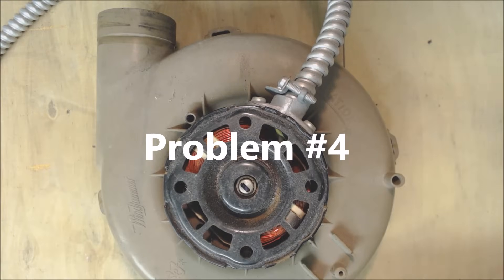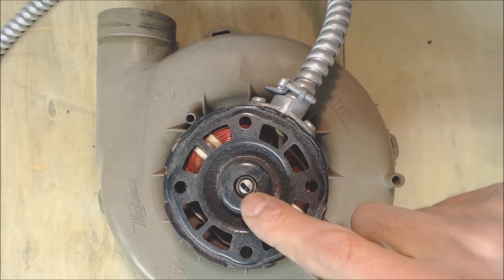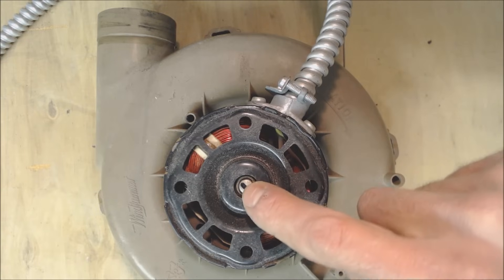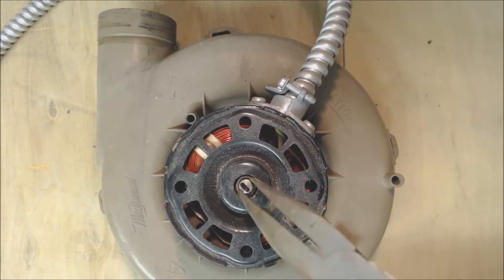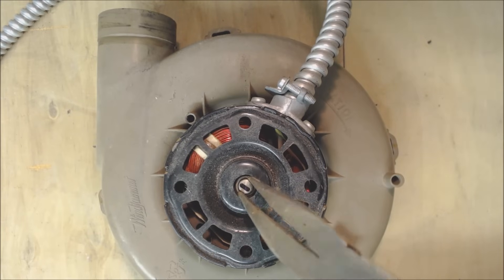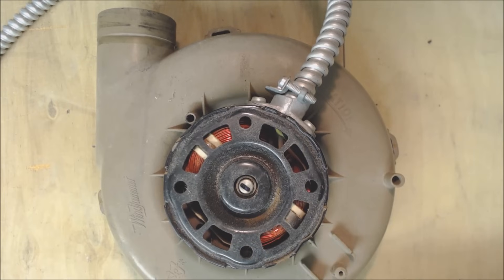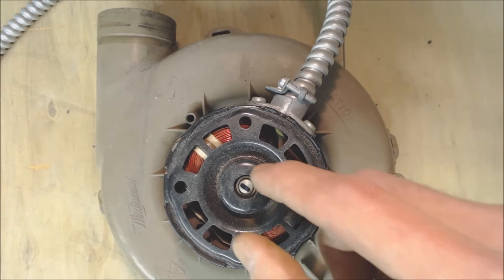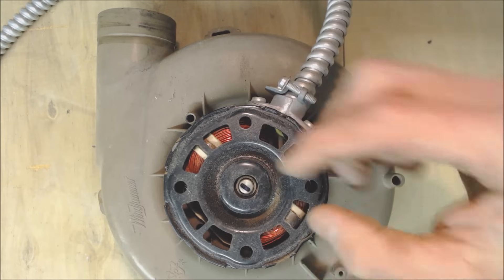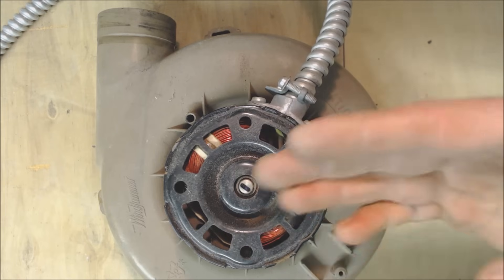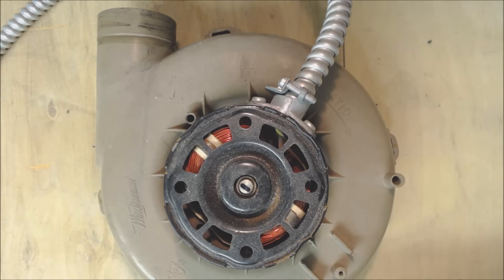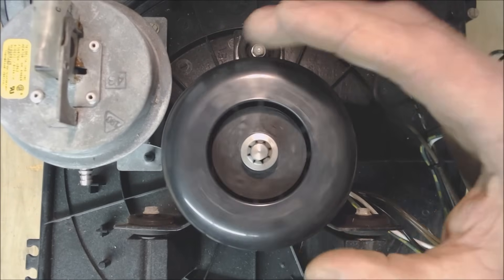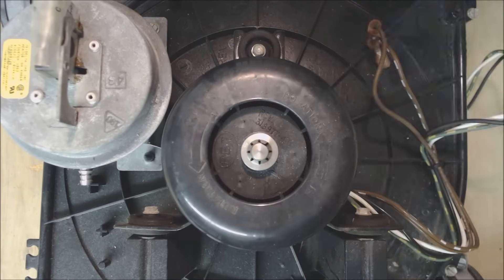So number four, the actual inducer motor bearings could be seized. So in this case, we can actually get into this shaft right here in order to try to spin it. And we see that that one's moving freely. But you can get into one and you can kind of feel it. It's really, really stuck. And once you get it spinning, then it seems to be working. A lot of times it's upon initial startup of the furnace for the first time in heating season. Other times it might just be in the middle of the heating season. You can tell this one is very easy in order to make sure that the inducer motor is spinning freely.